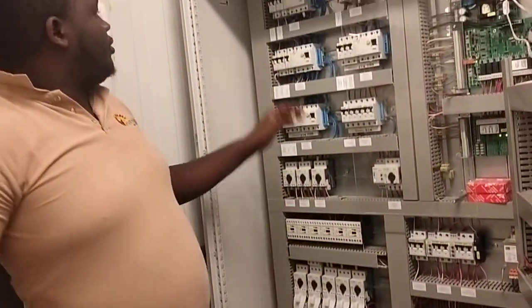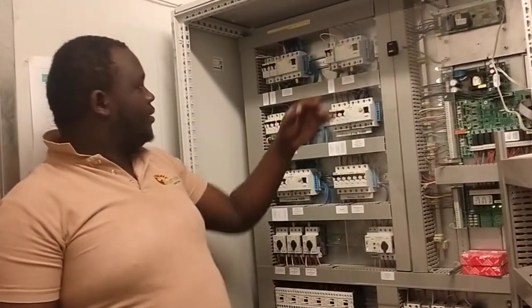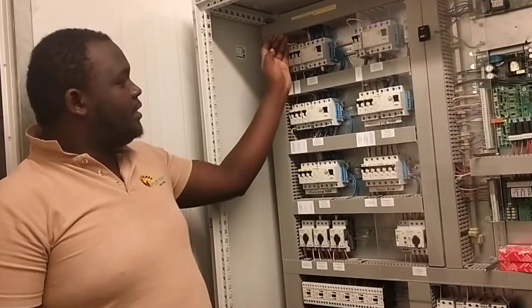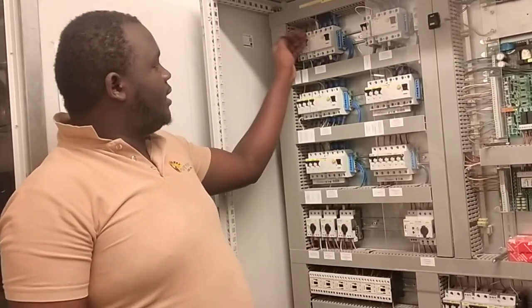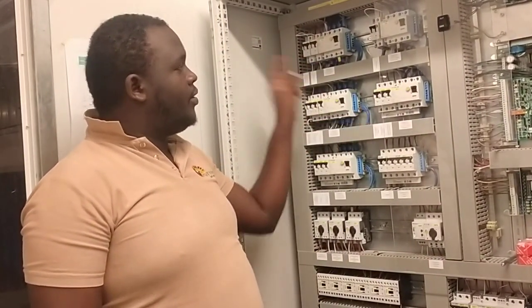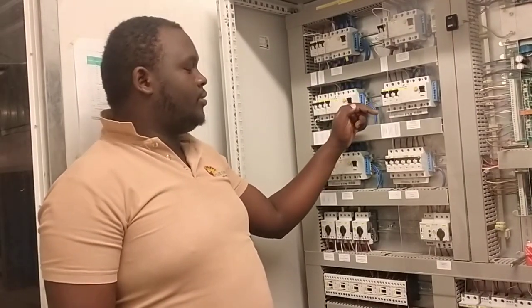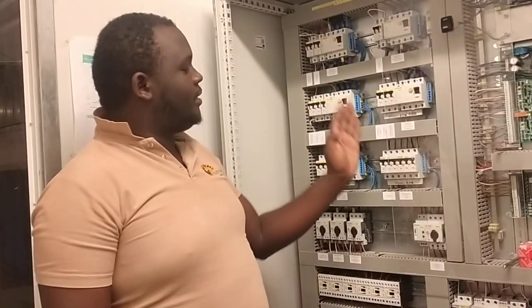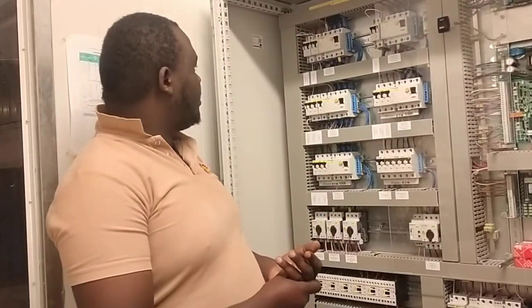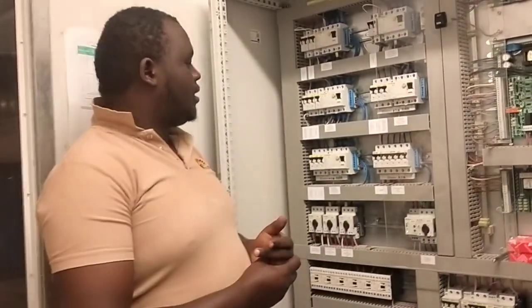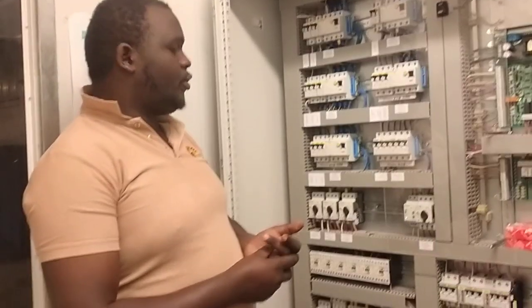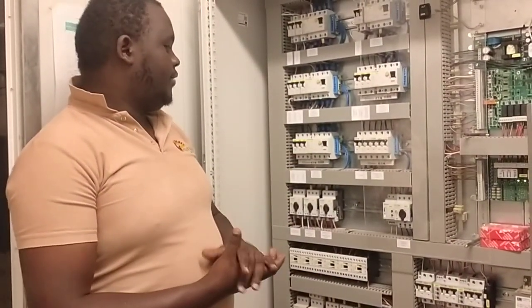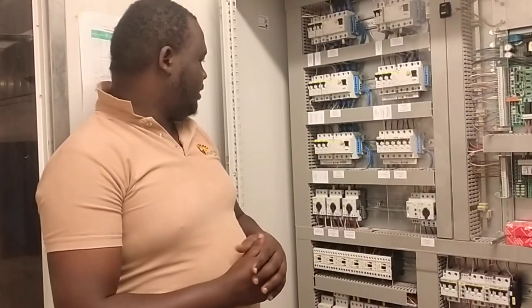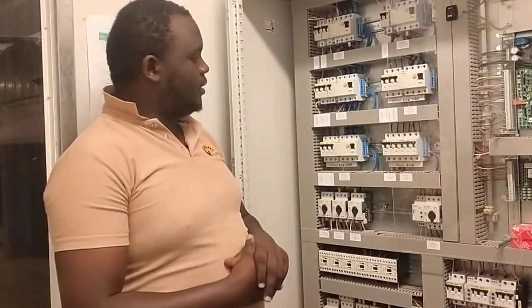So at the top here, you're going to see the first line. In the first line, we have what is called an RCBO. This RCBO will supply power directly first to the control phase controller. That is important to ensure that all three voltages are supplied to your motors, because in case the phase controller doesn't work, your motors will be supplied by maybe one or two phases, introducing the challenge of single phasing.